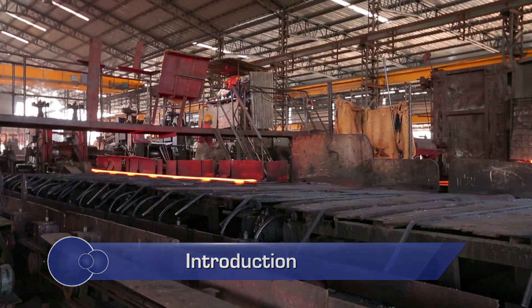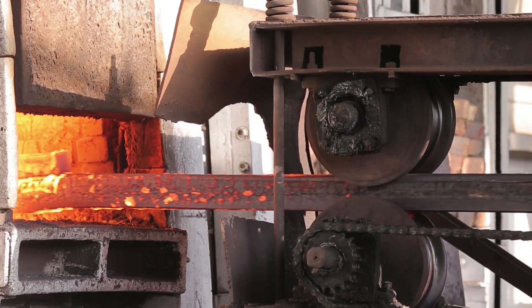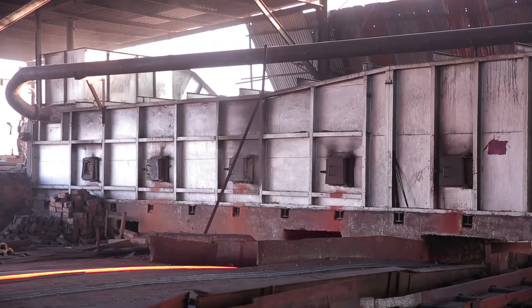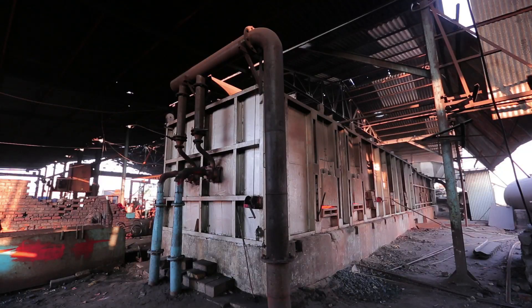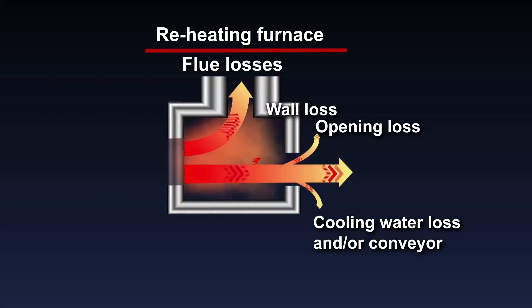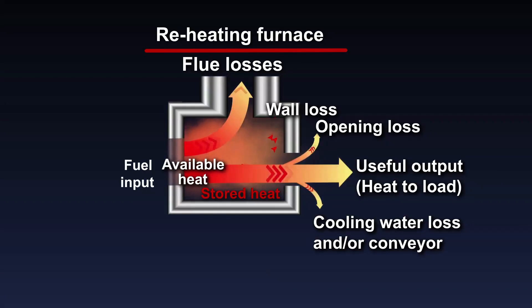Most of the steel rerolling units use top fired pusher type reheating furnaces with solid, liquid, or gaseous fuel. In a typical furnace, only 30 to 40 percent of the total heat input is converted to useful heat; the rest of the energy is lost through different areas and forms. The waste flue gas loss forms the major loss in a reheating furnace, accounting for 30 to 35 percent of the total heat input.